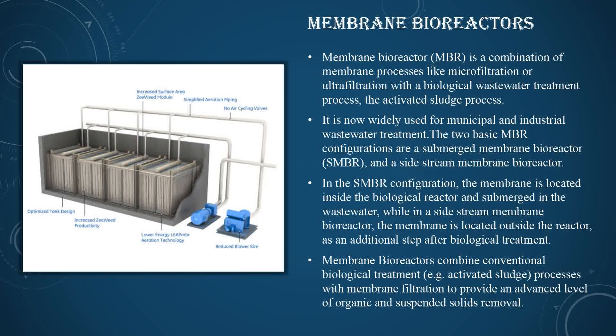The membrane bioreactor is a combination of membrane processes like microfiltration or ultrafiltration with a biological wastewater treatment process — the activated sludge process. In a submerged membrane bioreactor (SMBR) configuration, the membrane is located inside and submerged in the biological reactor and in the wastewater. In a side-stream membrane bioreactor, the membrane is located outside the reactor as an additional step after biological treatment.